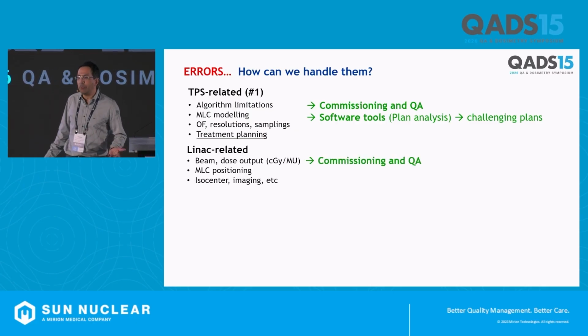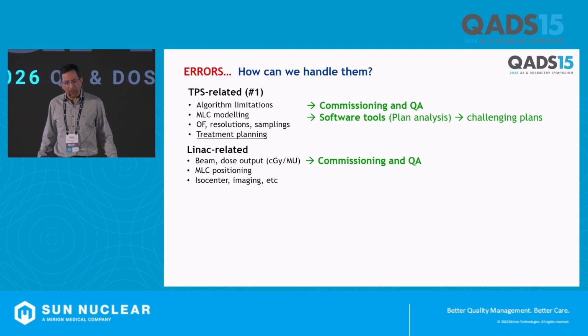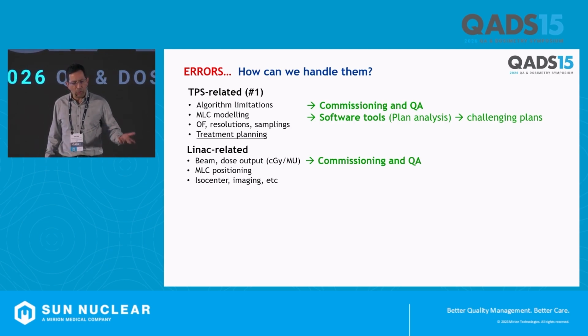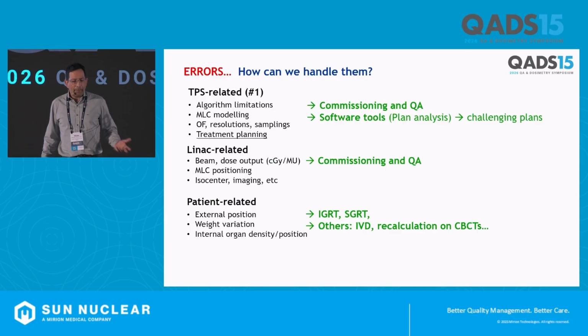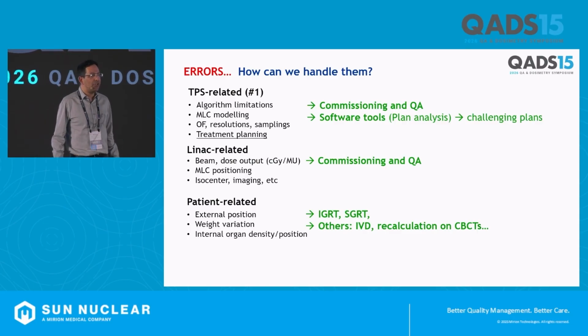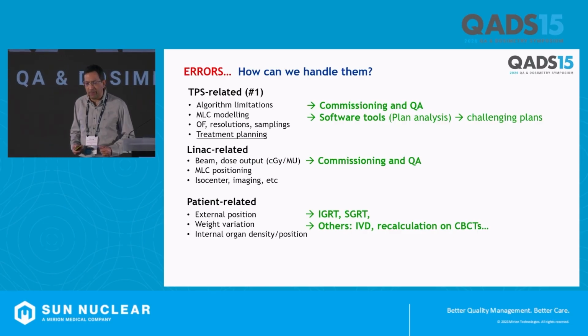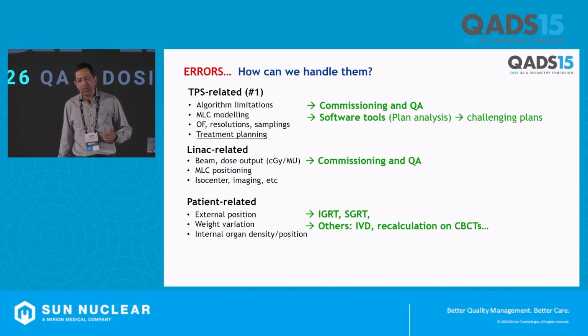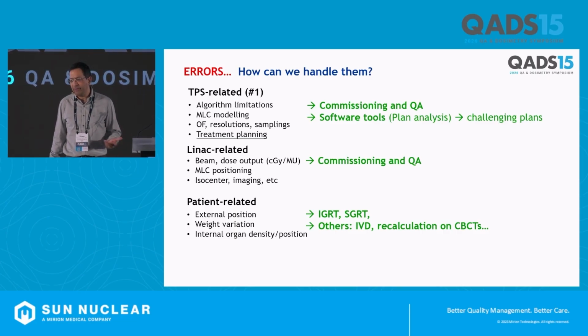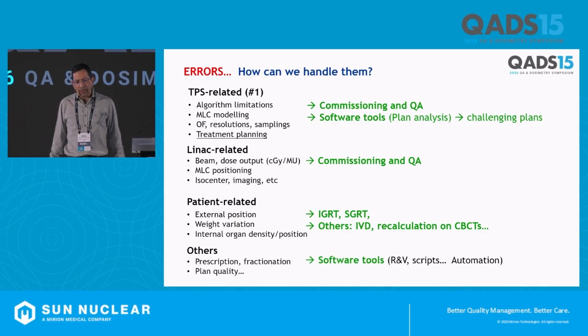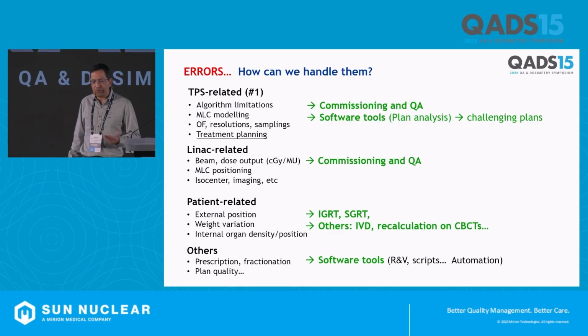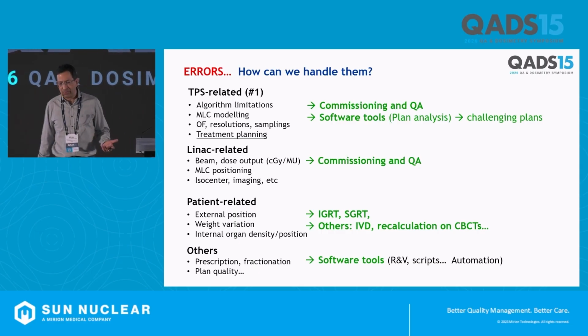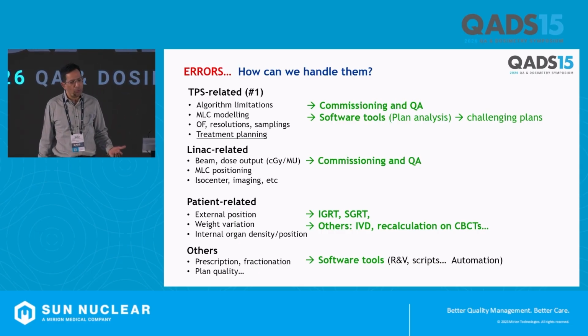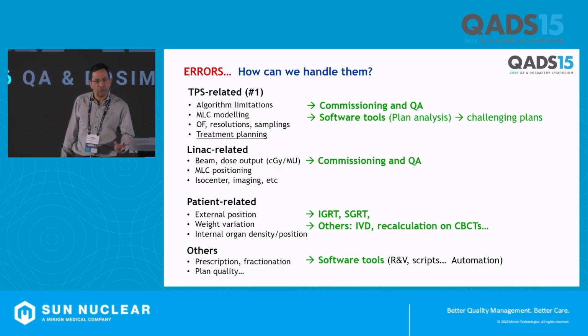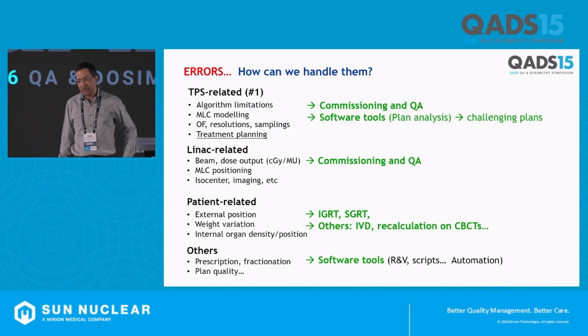Then you have LINAC-related errors, and that's very simple, that's clear. You need commissioning and QA. And patient-related errors, meaning errors in the patient model that you use in the TPS. For those, you need IGRT, SGRT, and you can also use, of course, in vivo dosimetry or recalculation on CBCTs. And finally, you can have other errors, meaning prescription or plan quality, other types. For those, software tools are important, record and verify systems, scripts that you may run and define, etc.